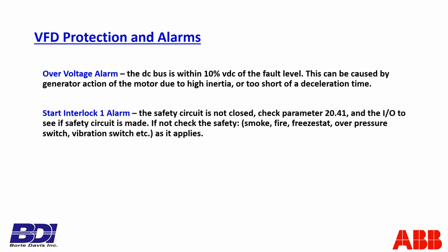The last item here is a start interlock 1 alarm. That is generally termed the safety circuit. Normally an application by default needs a safety circuit. Usually there's some kind of smoke, fire, freeze, or overpressure, or some sort of safety circuit that says if we see this condition, if we sense smoke, shut the system down, even though we have a run command, because we got smoke somewhere. Okay, so that's the start interlock alarm.